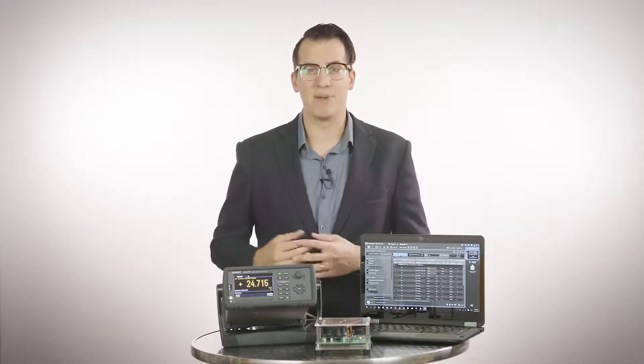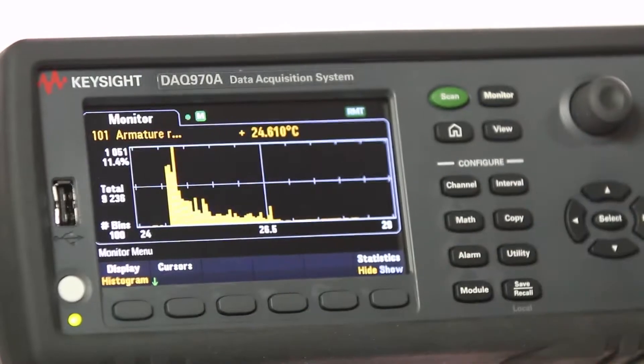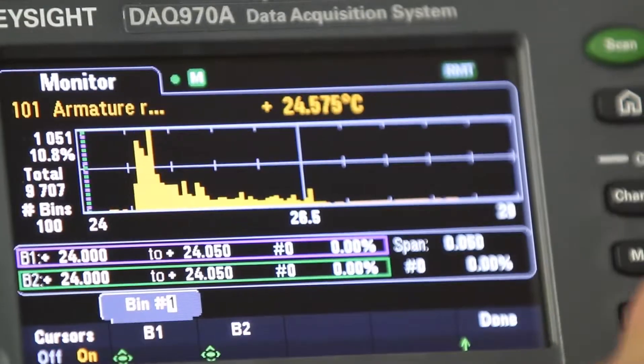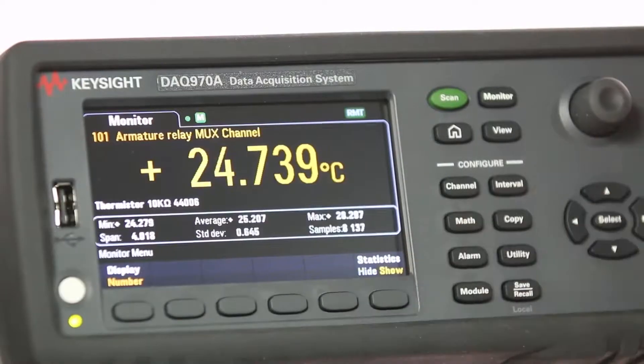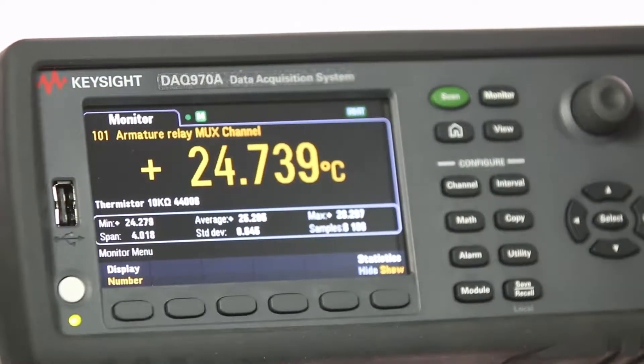The DAQ 970A has a built-in visualization toolset that provides more than just a single digital line readout. This toolset allows you to analyze data on a real-time basis. It can provide statistical data during measurements and you can view sample data results in numbers, trend charts, bar charts, histograms, and more.